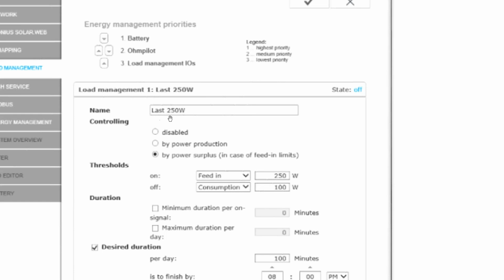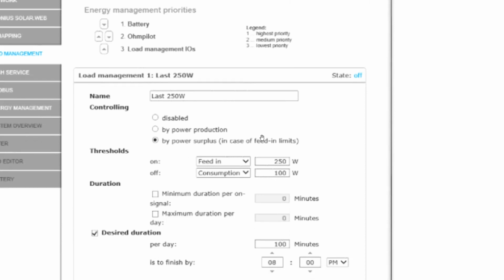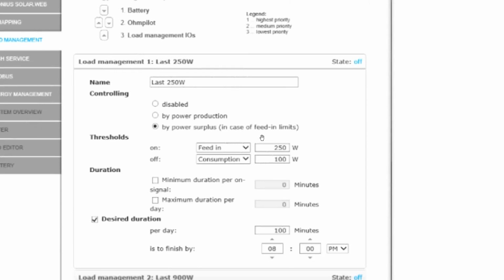So you can see here, the last 250 watts, we are going to activate a certain load that is connected to a specific relay that is switching it on and off. And then we say that our activation point, which is on, is when we have surplus energy of about 250 watts available. And then our off threshold is when we start consuming about 100 watts from the grid. So we can go in this manner and assign all the 4 IOs.